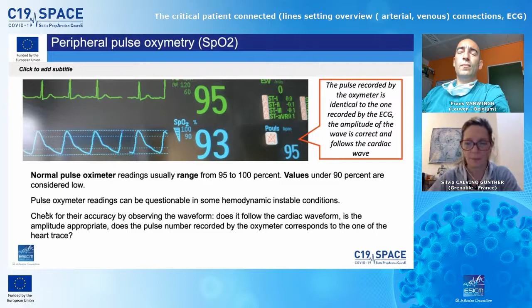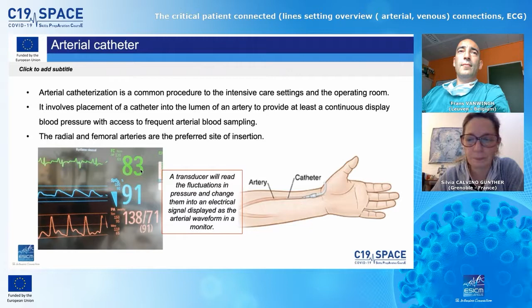Now we're going to see the arterial catheter. This one is already an invasive device. It's a common procedure in intensive care settings and the operating room. It involves the placement of a catheter into the lumen of an artery and provides at least continuous display of blood pressure with access to frequent arterial blood sampling. The radial and the femoral arteries are the preferred sites of insertion. So on one side you will have a catheter placed, and on the other side you will have a monitor. And in the middle there will be a transducer that will read the fluctuations in pressure and change them into an electrical signal displayed as the arterial waveform in a monitor.